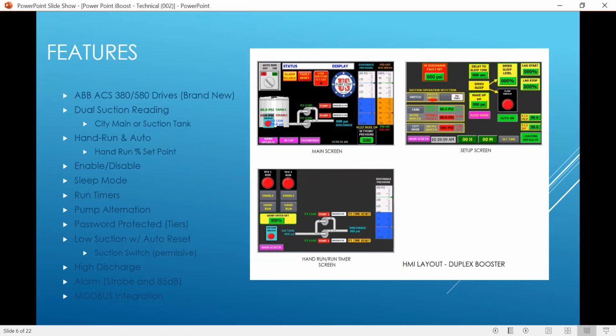Yeah, so we can actually do three different suction inputs, all from the same controller. The only thing that would be different from that point would be the sensor. We could use a typical city main where we're running off of a higher PSI. We can run off of a flow switch, which is typically done using a tank, but we can also use a tank and act more like a permissive using a submersible transducer. The submersible will show you the level in the tank, and you put a set point in there to make sure that the input is flooded. The pump will basically say, over this value I can run, once I go under that value, I can't run. And that'll be your low suction protection.